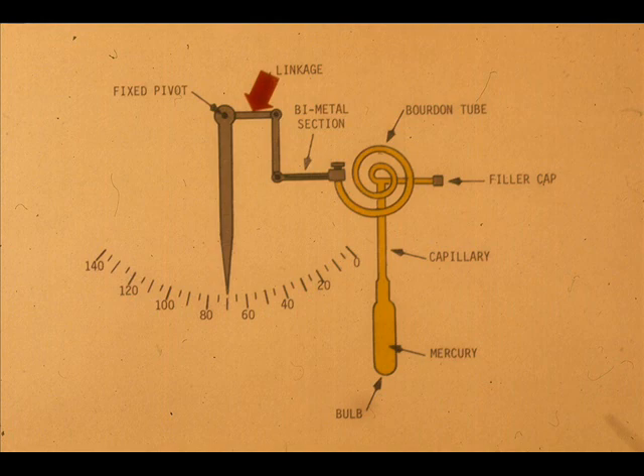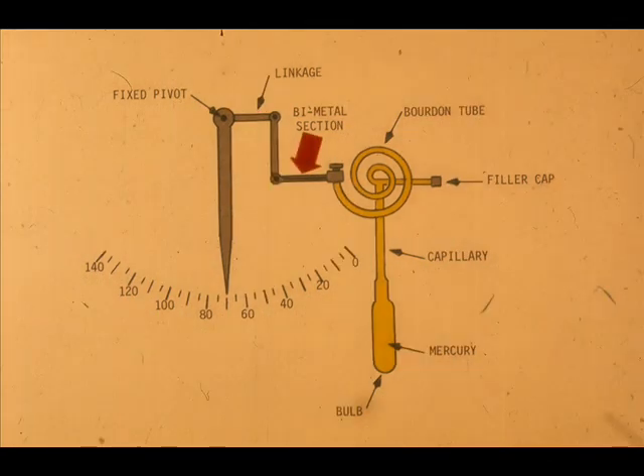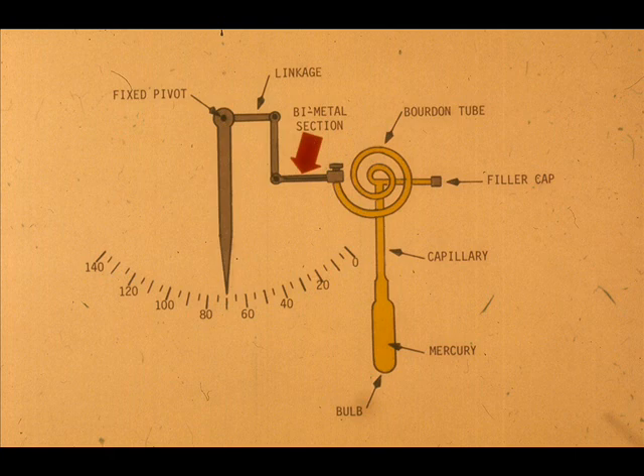The increased volume causes the Bourdon tube to unwind. The indicator, connected by the linkage, moves an amount proportional to the temperature increase at the bulb. Notice the bimetallic section of the linkage. This is to compensate for ambient temperature changes in the case, which would affect the Bourdon tube and cause an error in the readout.